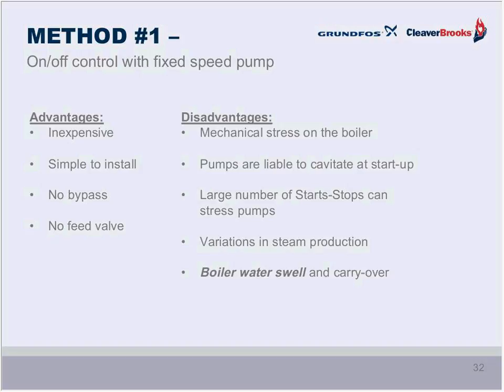But there are some disadvantages that offset this simplicity. The stresses on the boiler. The pumps have to operate across a pretty wide range on their curve, and they can encounter situations where they'll cavitate, and that's really hard on the pump. A large number of starts and stops, like it says, can stress the pumps and the motors.